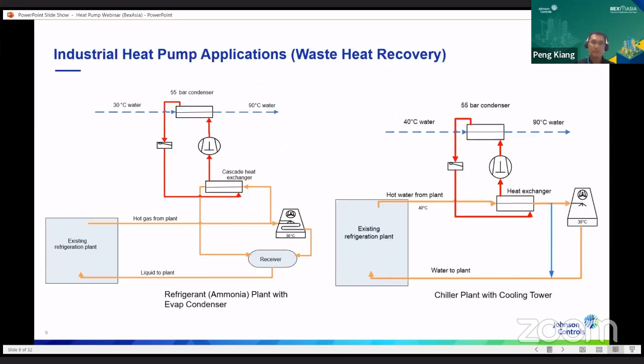Now, another classic example is if you can combine cooling and heating together in a process in a plant. For example, the one on the left is a very matched capacity, which means that whatever cooling capacity you get out of the heat pump, which can cool water, for example, from 15 to 7 degrees C, you could also produce energy on the other side as heating capacity for what is required in the plant.